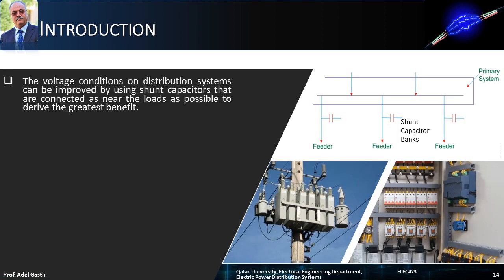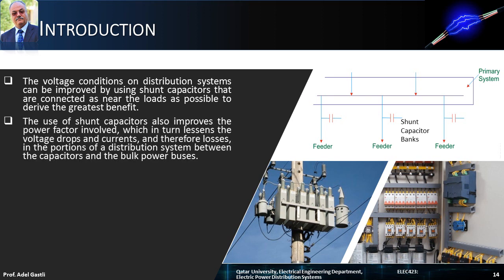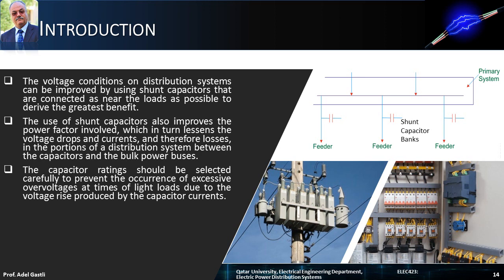The voltage conditions on distribution systems can be improved by using shunt capacitors that are connected as near the loads as possible to derive the greatest benefit. The use of shunt capacitors also improves the power factor involved, which in turn lessens the voltage drops and currents, and therefore losses, in the portions of a distribution system between the capacitors and the bulk power buses. The capacitor ratings should be selected carefully to prevent the occurrence of excessive overvoltages at times of light loads, due to the voltage rise produced by the capacitor currents.